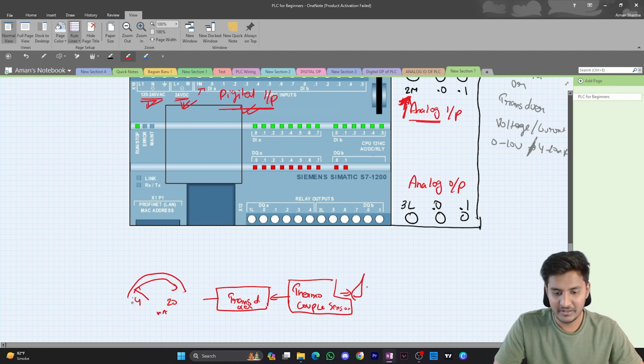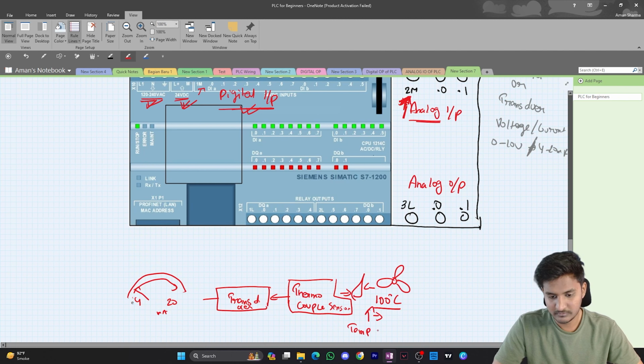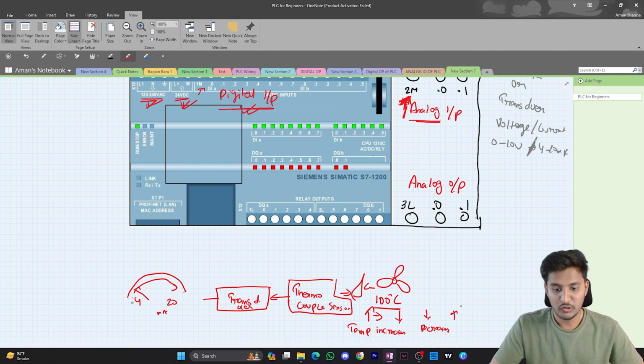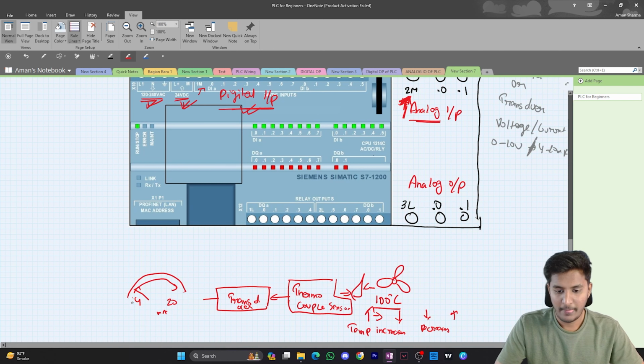And we have programmed our PLC such that the temperature of the heat should be maintained at 100 degrees Celsius. So near the heat we have our fan, and if the temperature increases, the speed of the fan decreases. So the flow of air should be reduced to control the heat, and vice versa. If the temperature decreases, the speed of the fan increases to increase the flow of air to force the combustion to increase the temperature. So now we have our input, but we need to control the speed of the fan as per the temperature changes.